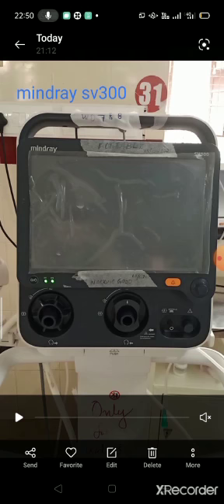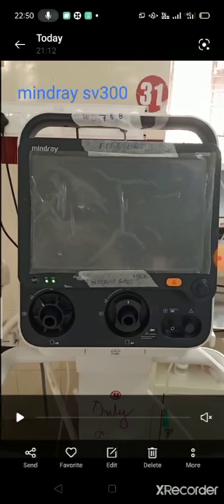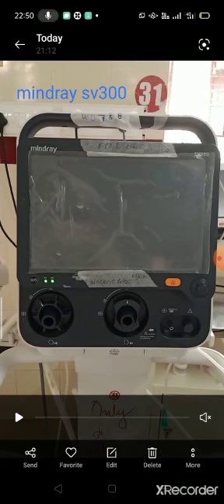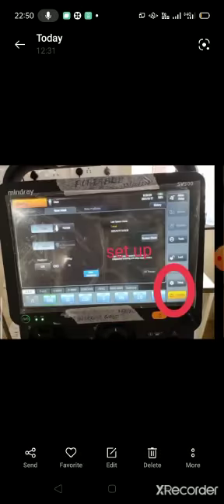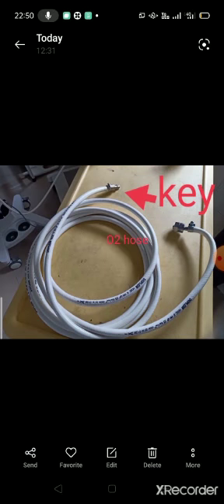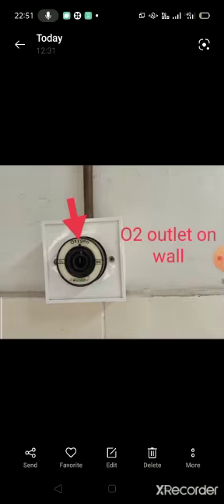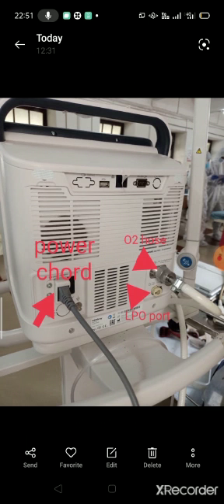For this ventilator you have two connections which need to be connected, that is the AC power supply through the power cord and the O2 hose. So this is the O2 hose that you have to connect. You can see it at the machine backside, and you have to check which key is available, whether it suits the O2 outlet available with you. This is the O2 outlet to which this O2 hose needs to be connected. And this is the back side of the ventilator where you can see the power cord. The O2 hose connection is there, which will be connected to the O2 outlet at the wall.